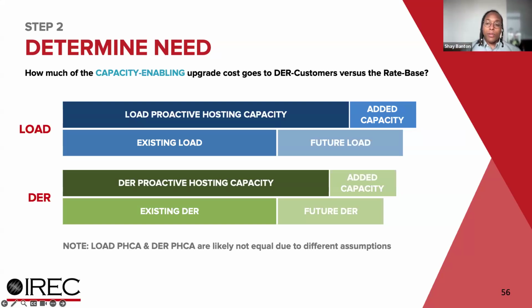Under a typical distribution planning process, we're focusing on two variables. Future load is higher, so we need to increase capacity. The top line, load proactive host capacity, is the value of the current system under those future loading conditions—what is the capacity of the system for new load? If you breach that value with new or future load, you have to add capacity. So if existing load is below the load proactive host capacity threshold, but future load pushes it beyond, added capacity is now necessary—an investment is now necessary.